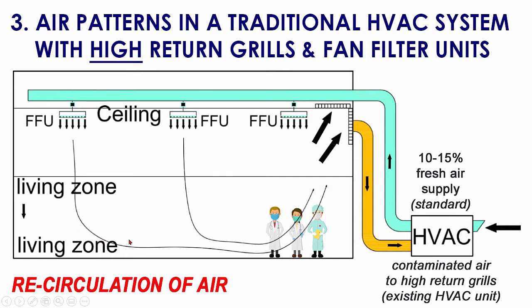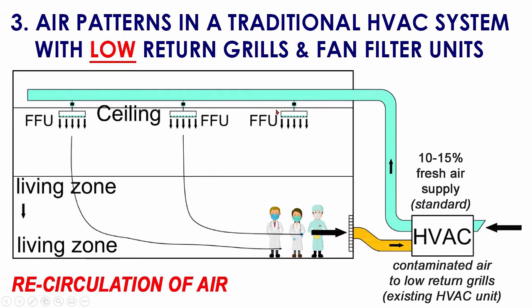You can see the air is moving through the living zone and picking up contaminants and is rising toward the high ceiling or high wall returns. This is a risk, but as the air is circulating, it's being cleaned by the fan filter units. So that is an advantage. Let's look at what happens if we lower the return grills. We can see right away that the air pattern has changed. The air is dropped into the living zone and moves through it, picking up contaminants, bacteria and viruses and other contaminants, and moving to the low return. This is an advantage because the air is low and the risk for medical personnel to get infected is lower.